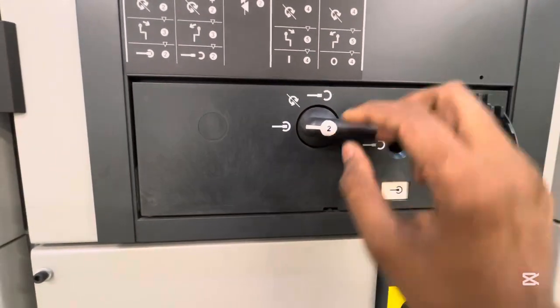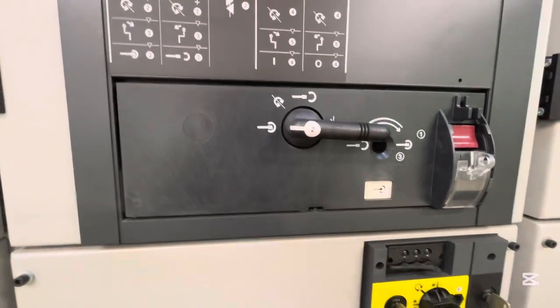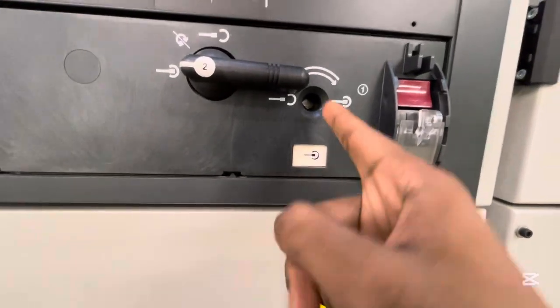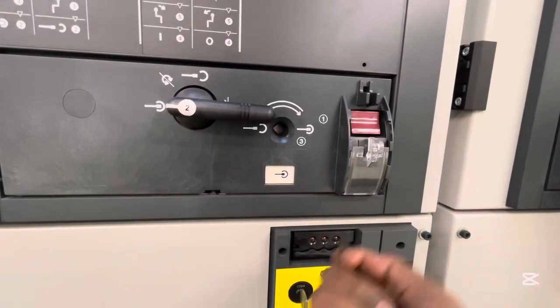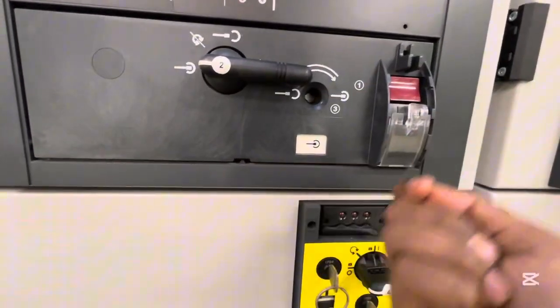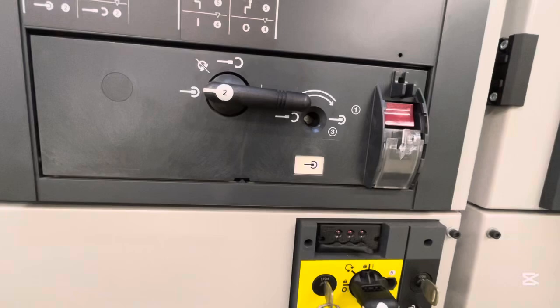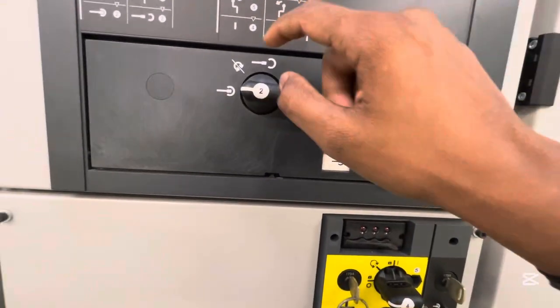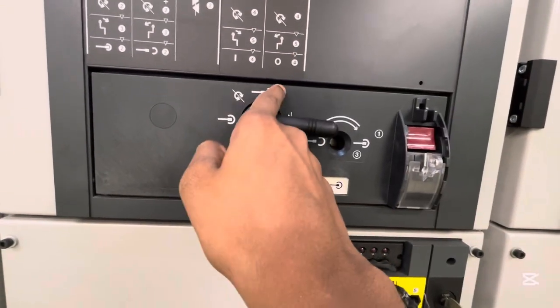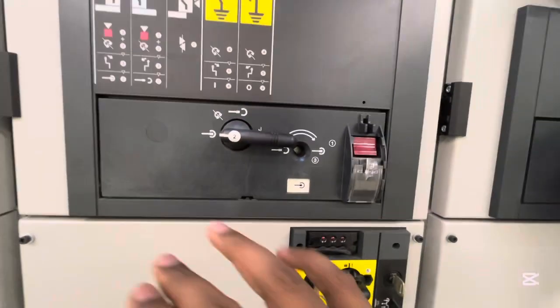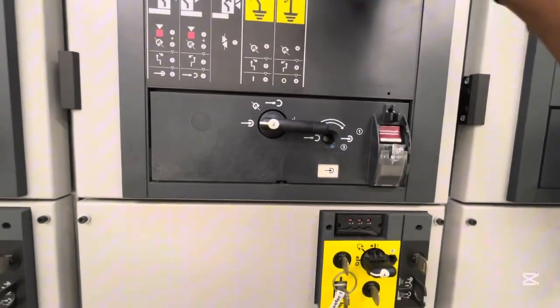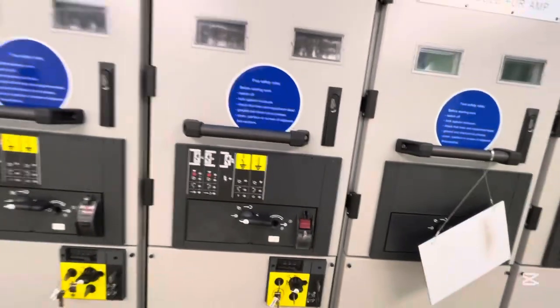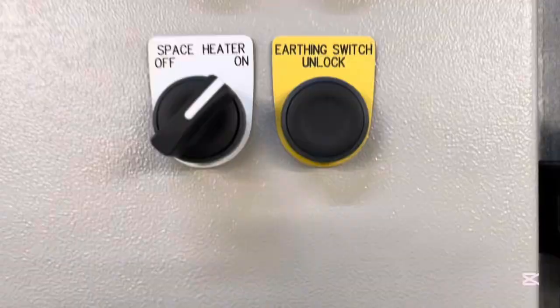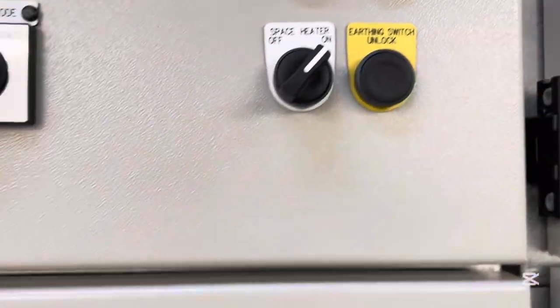That red switch, first you have to press it down, and the lever here is in the engaged position. You make it go to the center disengage position, then insert a rod in the hole and rotate it from engage to disengage. As you rotate, the circuit breaker actually comes out, gets racked out, and you can confirm this through the inspection holes. The next step is to press the earthing unlock switch.